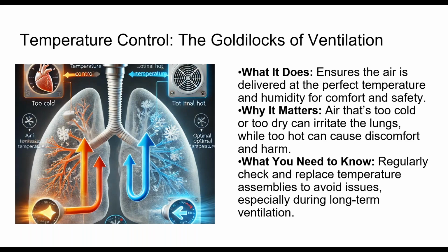It's equally important and often forgotten that the heated humidifiers are a central component to good delivery of care. So regularly check them and replace the temperature cells, the temperature assemblies, the sensor wires. There's a common brand out in use right now that has a PM requirement that actually checks the temperature cells or the temperature sensors. If you are familiar with Fisher-Paykel's preventative maintenance procedures, they have you check those sensors too. If you have not, I caution you on this: if you have not had a plan of tracking how frequently they've been used, how many times they've been used, and say disposing of the sensors themselves before you come up to the PM instance of it. I think it's annual on those.